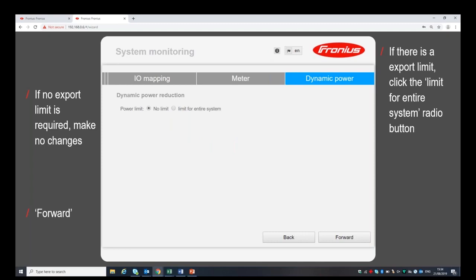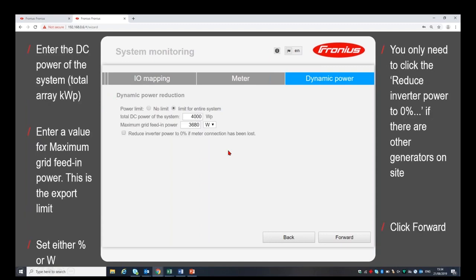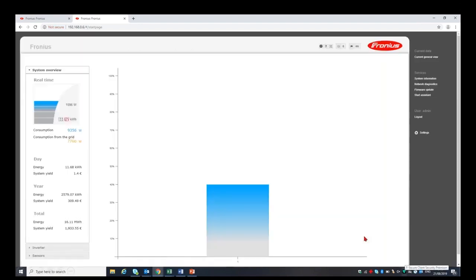And then the next page is to go to the dynamic power reduction. So as a standard, we allow all energy to go back to the grid. There's no limit on power export. We can change that to the limit for the entire system. We can set the power of the PV system, so that's for the array up on the roof, and then the maximum amount of energy that can go back to the grid. So typically for a single phase system under G98, we'll set that to 3,680 watts. Once you've done that, click forward, and you'll go back to the main overview page on your data manager.